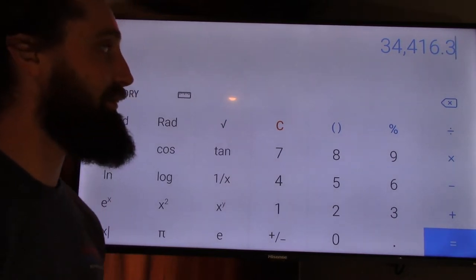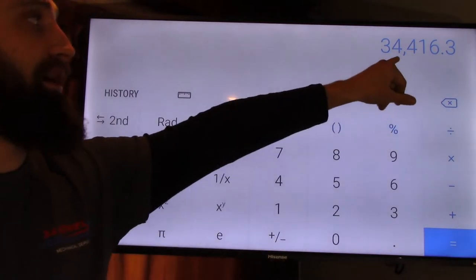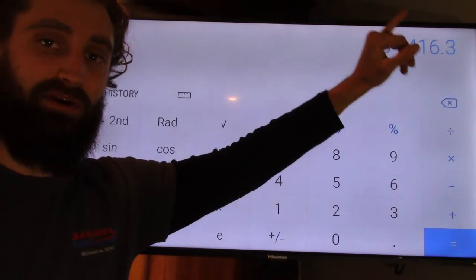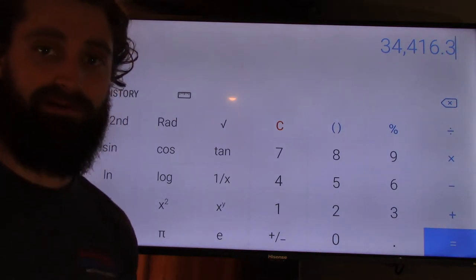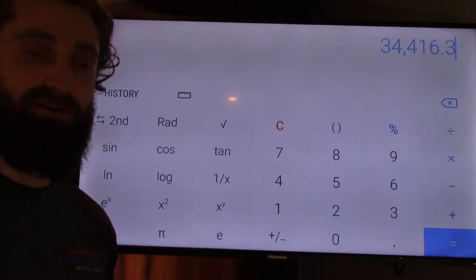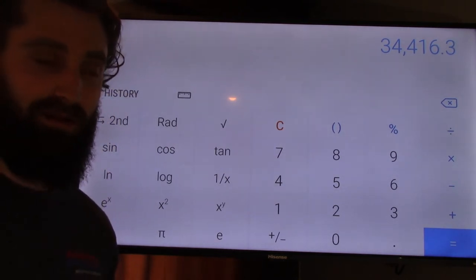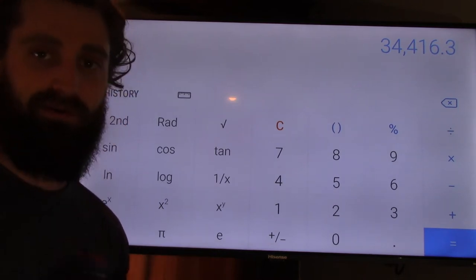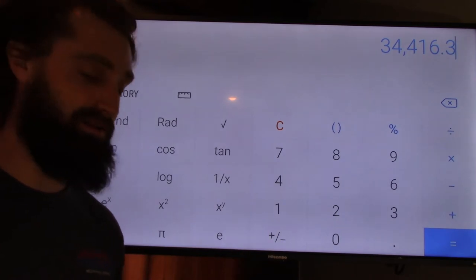Imagine that, okay? Just 89 CFM made that much difference in our equation, and you're going to see that extrapolated whenever we're talking higher capacity systems. Let's say we were off that much on a 5-ton unit or a 10-ton unit, okay? It is very critical that you take accurate readings whenever you're trying to figure out capacity on a system.